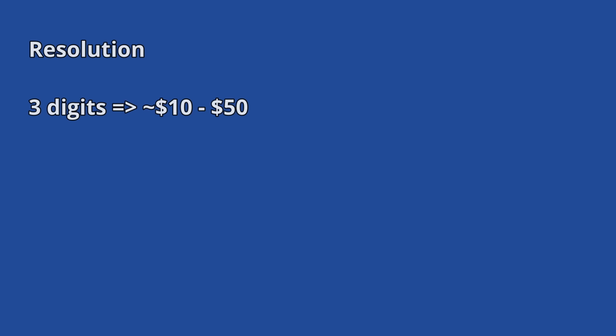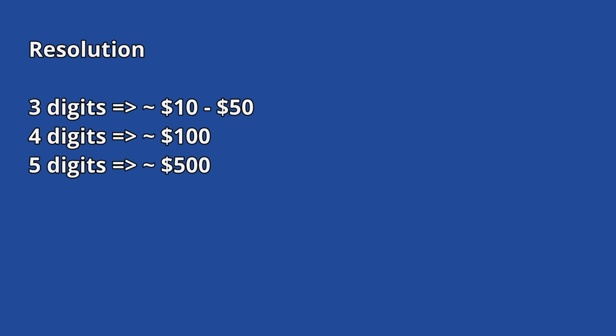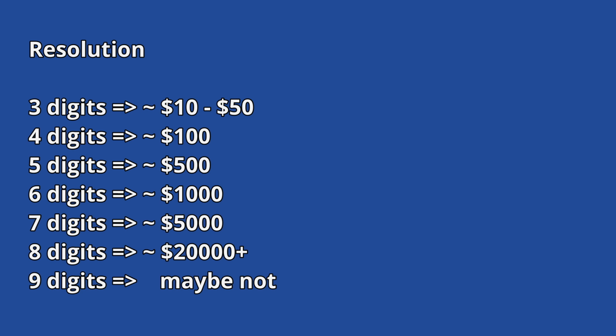Resolution is the most significant factor that influences the price of a multimeter. The cheapest multimeters have a solid 2 to 3 digits of resolution and sell for under $10. As the number of digits of resolution increases, so does the price. 4 digits of resolution is about $100, 5 digits is about $500, and 6 digits will cost about $1,000. Beyond this, there are meters with 7, 8, and 9 digits of resolution, with exponential increases in price.